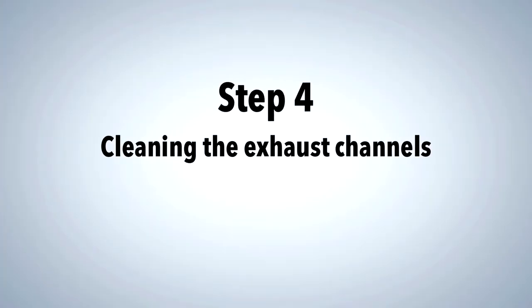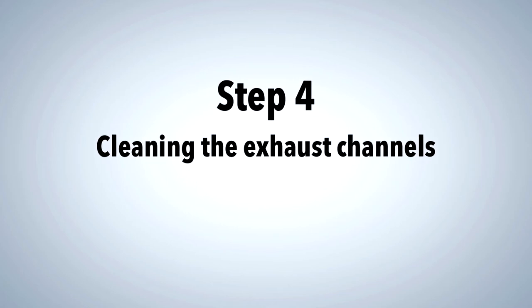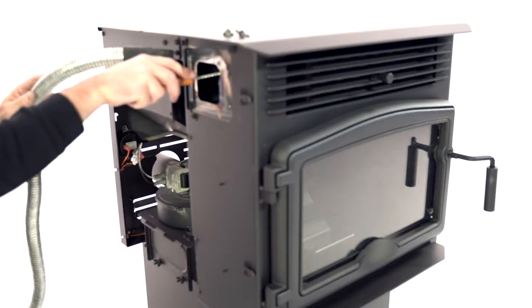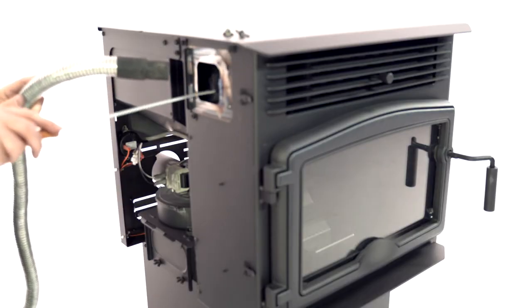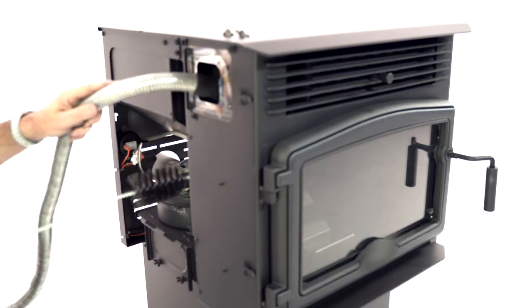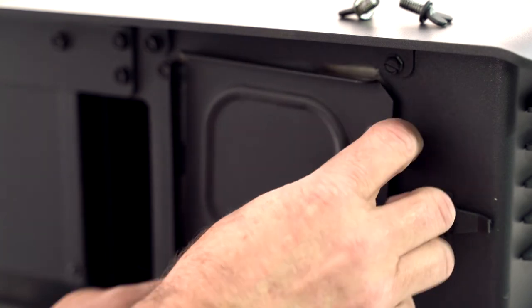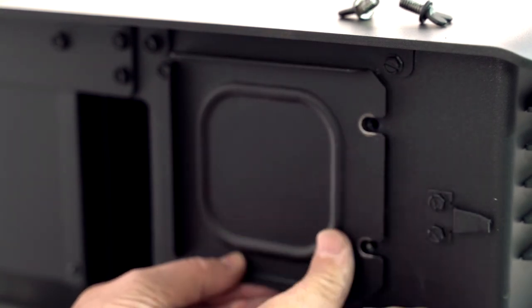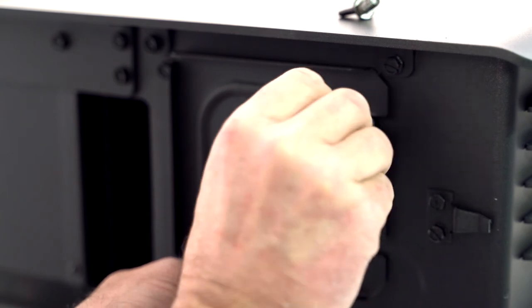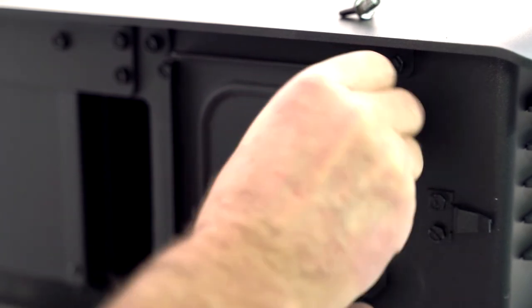To access the side exhaust pipes, remove the left decorative panel. Remove the top access cover and clean the channel with a brush and an ash vacuum. Once completed, reinstall the cover and tighten the bolts properly. An unsealed lid can lead to dust leakage or smoke odors.